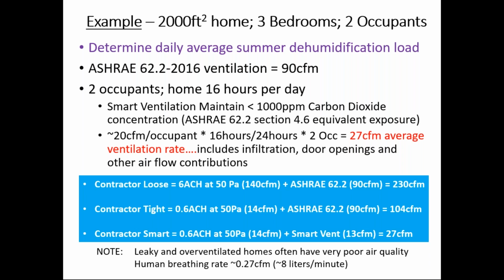And if that occupant, in order to maintain 1,000 parts per million, is in the house 16 hours a day out of 24, we would need about 27 cubic feet per minute average ventilation rate, which also includes infiltration, door openings, window openings, and other things that are contributing to air blowing through one's house. So if you have kids and they're regularly opening and closing outside doors, or a pet, or you're not opening them, there's a balance between either the ventilation system or the infiltration that adds up to what you need to manage the indoor air quality. And this is what a smart ventilation system does as far as maintaining your pollutant exposure.